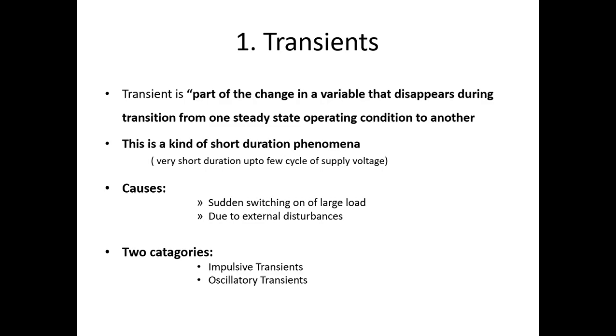This is a short duration phenomenon, lasting up to a few cycles of the voltage supply. You will get changes in the supply voltage, and these are called short duration voltage variations. Now, what are the causes of transients? Sudden switching on of a large load. If you suddenly switch a large load, or open the isolators, there may be a chance of short duration voltage variations. That means you will get a voltage variation for a short duration.